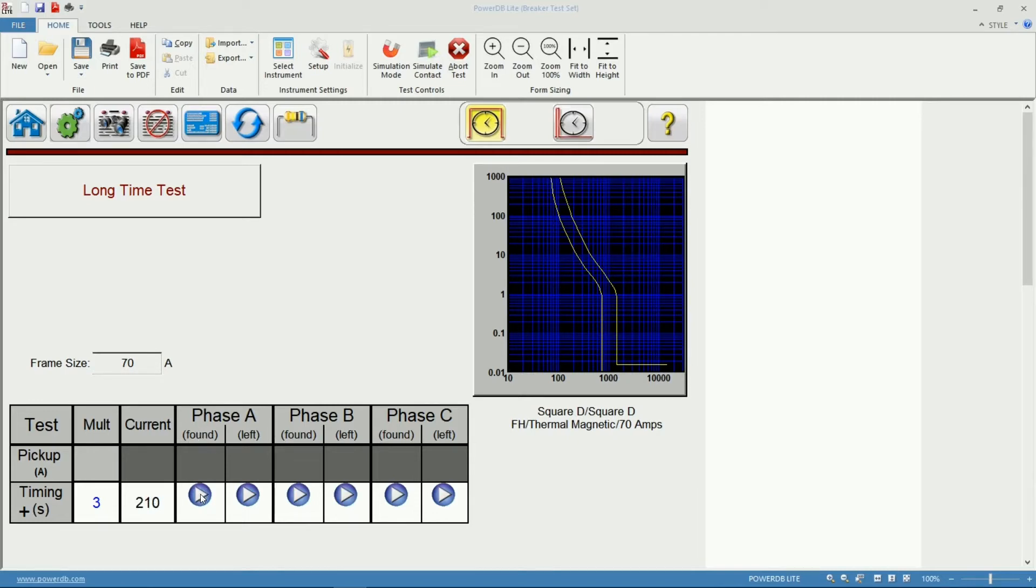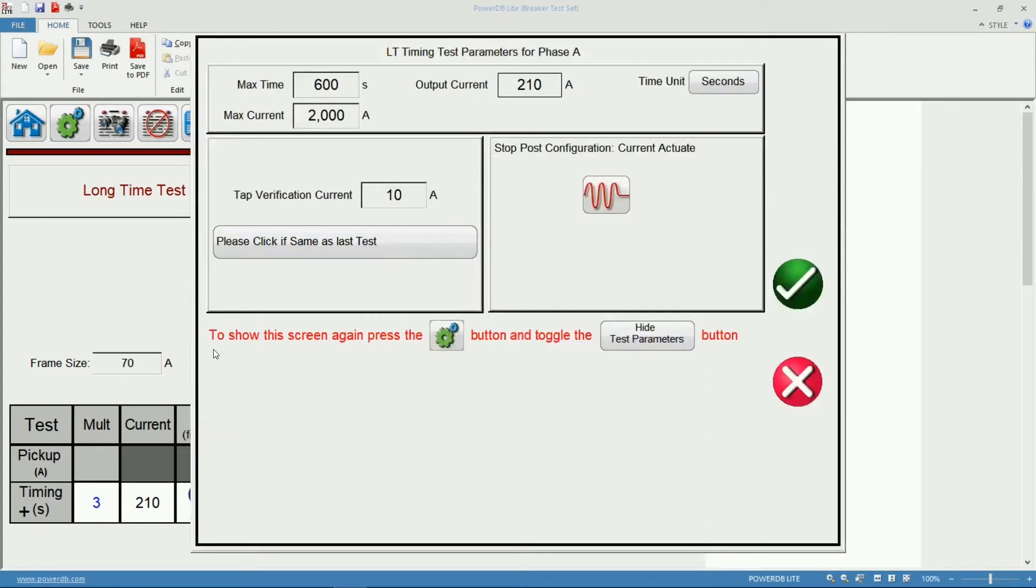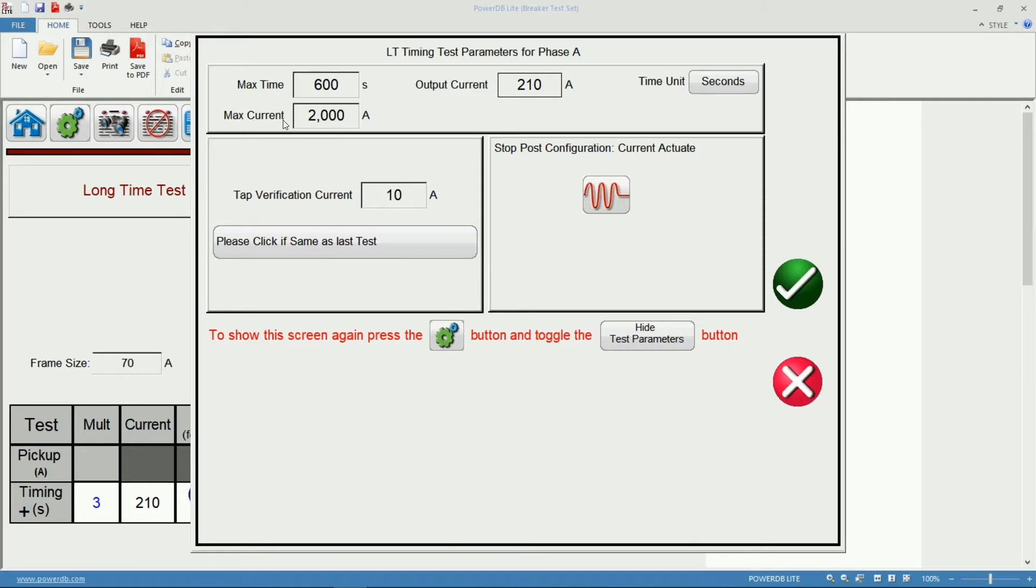Let's go ahead and start with the Phase A Test. I'll click the Play button here. Since this is the very first injection in this session, the software is asking me to confirm some of the settings for the output, the maximum time allowed, the maximum current allowed. It's indicating the test that it's going to use and I can also change the TAP verification current.